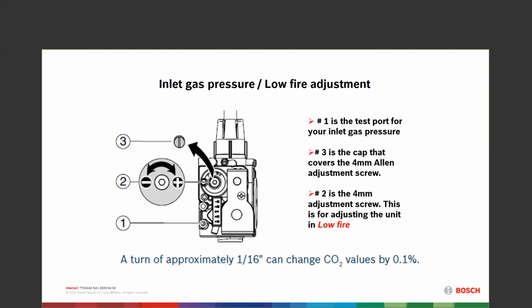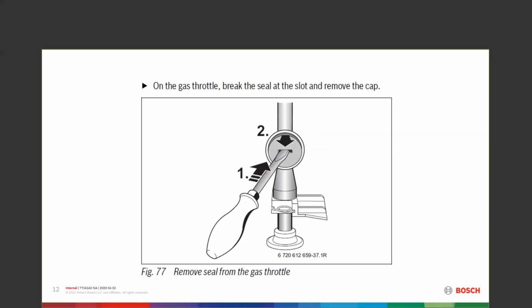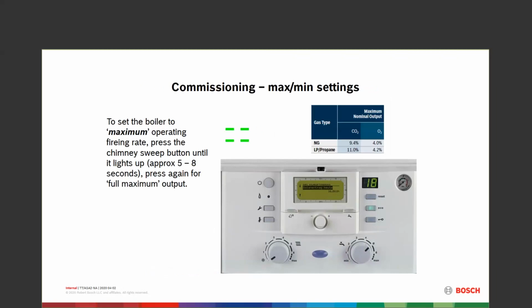When you get to the high pressure side of it, you've got a gas throttle and it's got a gray plug seal in it. You're going to break that seal out. Most of the time you have to push a screwdriver or something through the slot in it. That will break it out and get rid of that piece. Once you take that out, you're going to have a slot inside there to adjust with, and you're going to go back into this control.